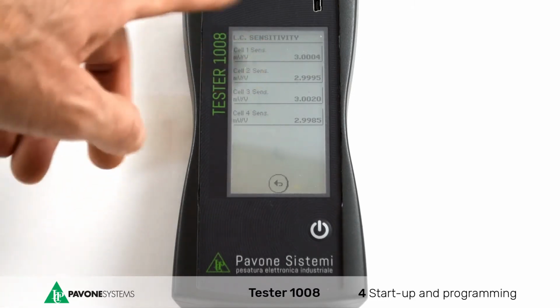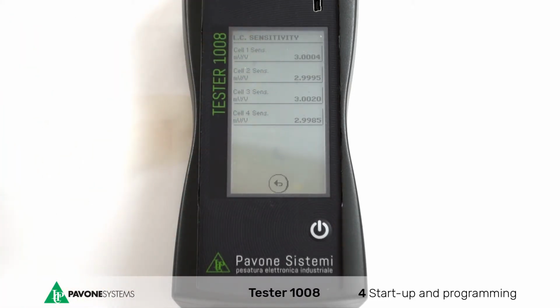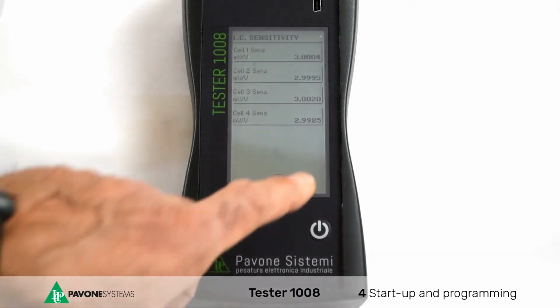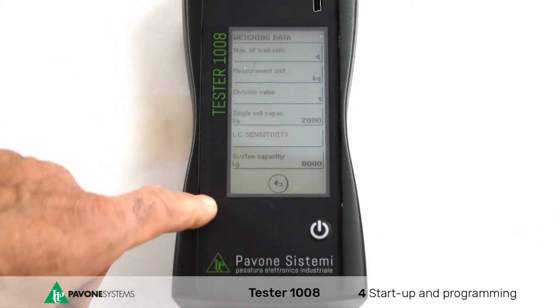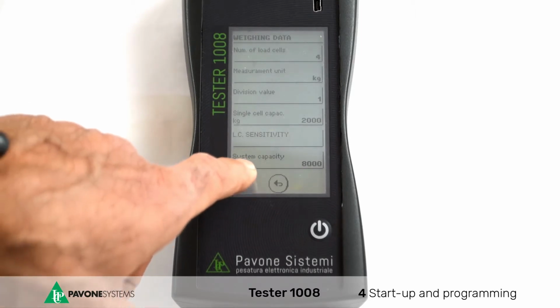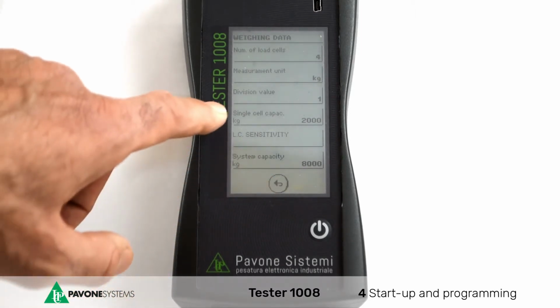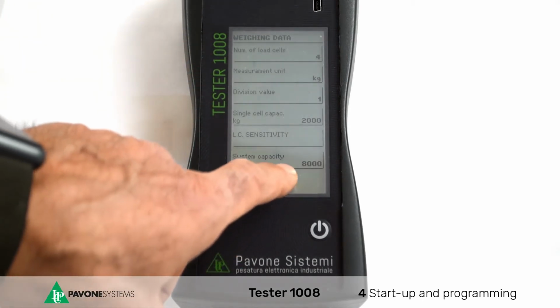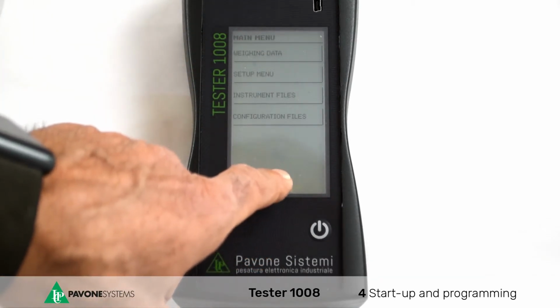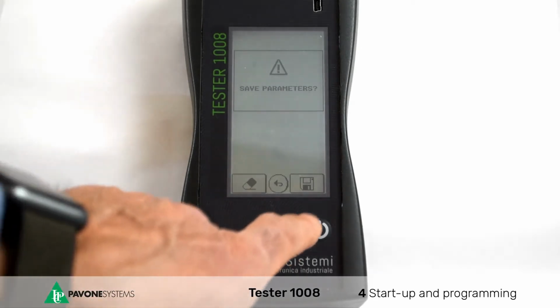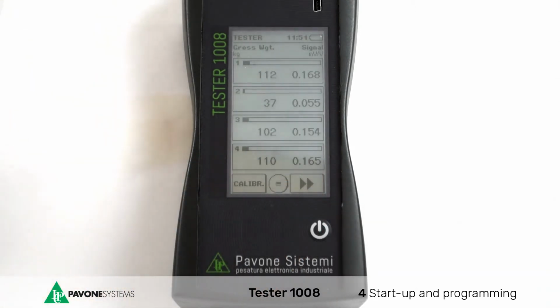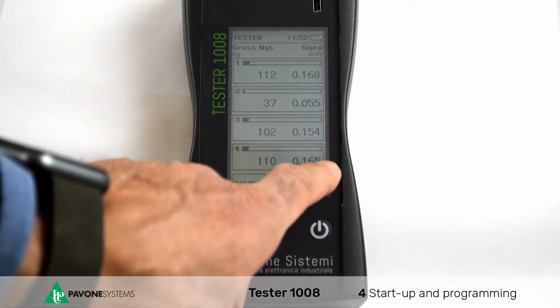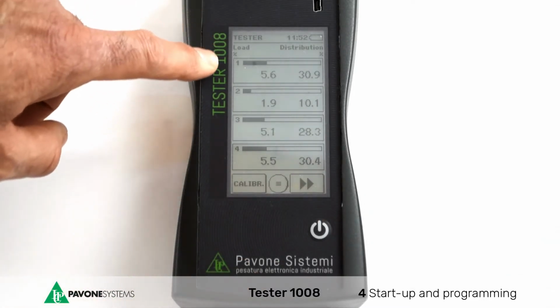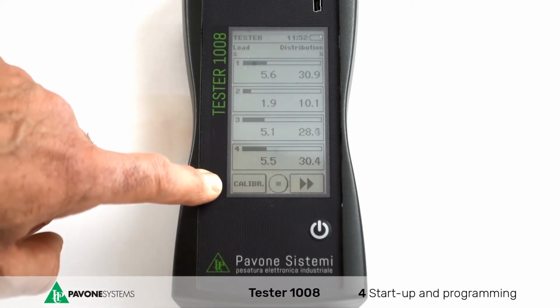Now, set the sensitivity of every single cell. In this case, the cell number 1 has 3.0004, cell number 2 2.9995, and so on. After that, the system capacity, or rather, the sum of the single cell capacity, in this case 8,000 kilograms. Close the menu and save the data pressing the key at the bottom on the right. At this point, you will be able to see the single weights and their distribution with the desired measurement unit. In the screen number 2, the load values expressed in percentage will be also updated.